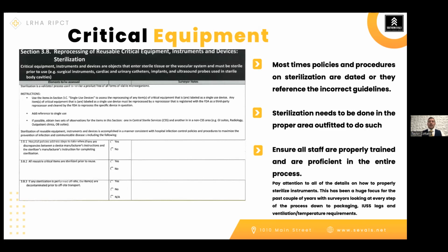Sterilization needs to be done in a proper area outfitted to do so. So if we have an autoclave just stuck in a storage room, is that the proper area? Is there ventilation in there? We need to think through that. Sterilization in a central sterile area, we need to think through traffic from dirty to clean. We're going to touch on more, but make sure that any sterilization that you're doing, whether it's in a clinic setting or in a hospital setting, is done in a proper area that is outfitted to do so. There are ventilation requirements, there are temperature requirements. You want to make sure that you become familiar with those, or that you talk to your facilities manager, and you can look those things up to make sure you're following within compliance.